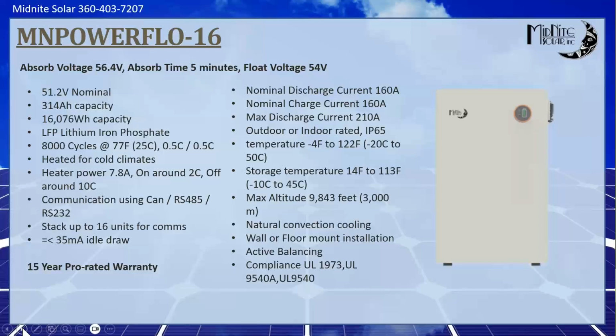Now I was even asked this question, or I asked this question early days, like, does the heater just run all night and drain the battery down? Well, it turns out the answer was no, the heater only runs when there's charge current available to run the heater. So if you have 300 watts of PV and the battery's sitting at 10 degrees below zero, then the heater is going to run and all that PV is going to run the heater. Nothing's going to go into the battery. If you have 500 watts, then 300 will go into the heater and 200 will go into the battery, and so on and so forth. Again, same communications: CAN bus, RS-485, RS-232.